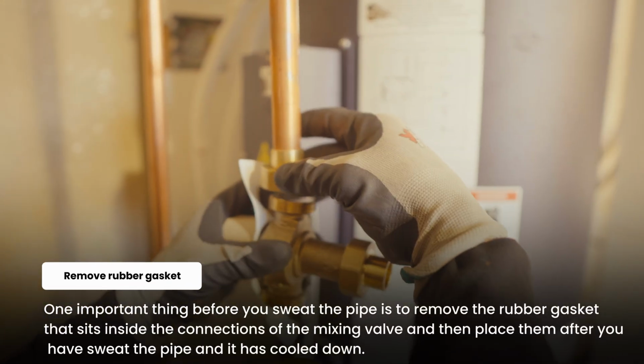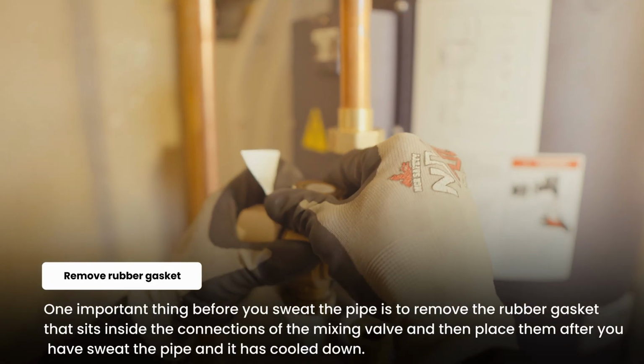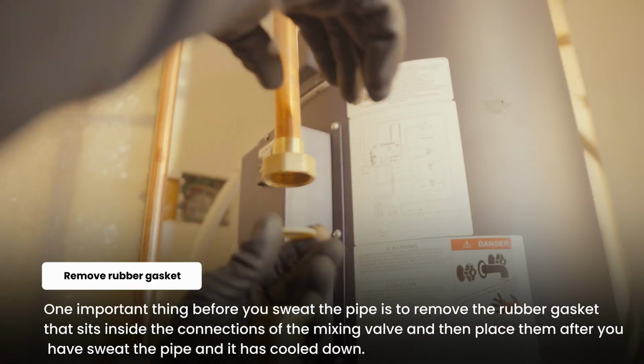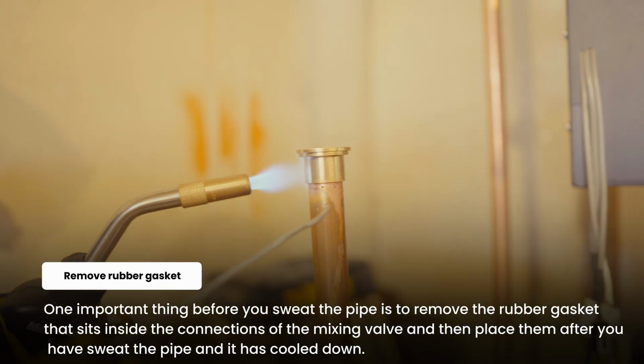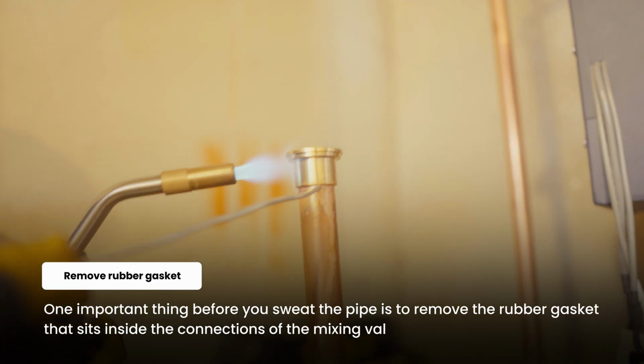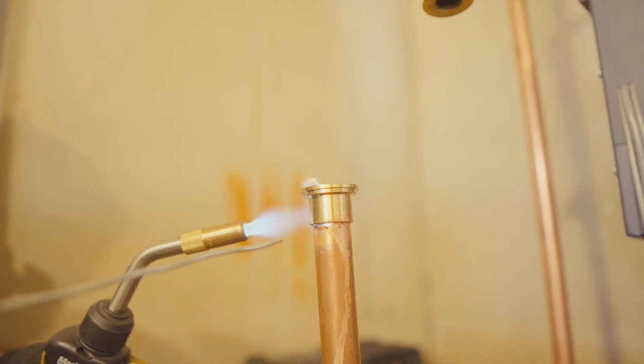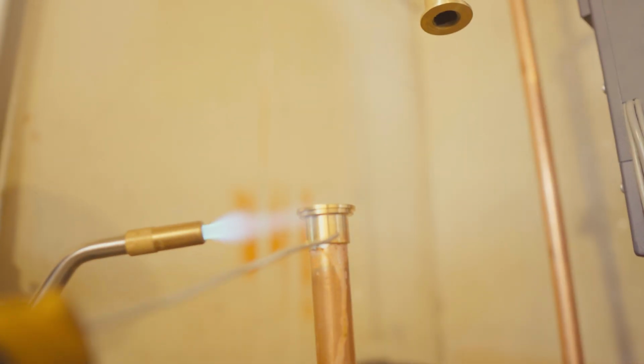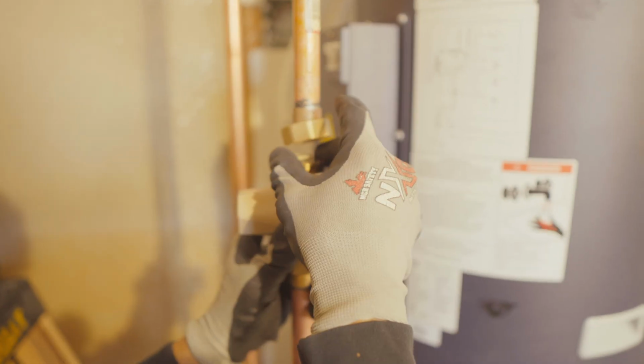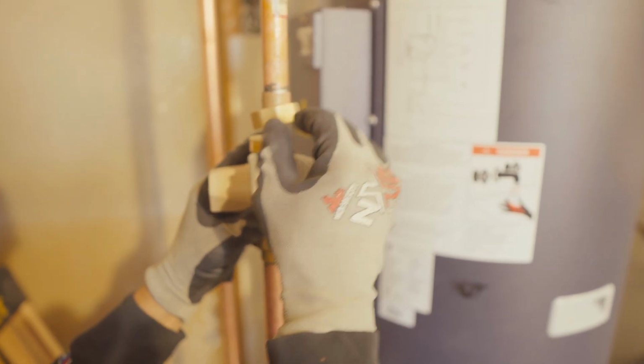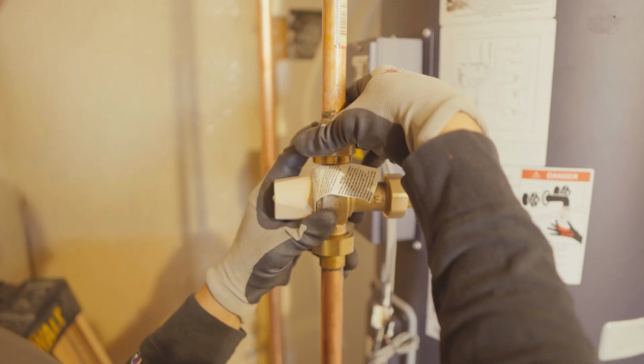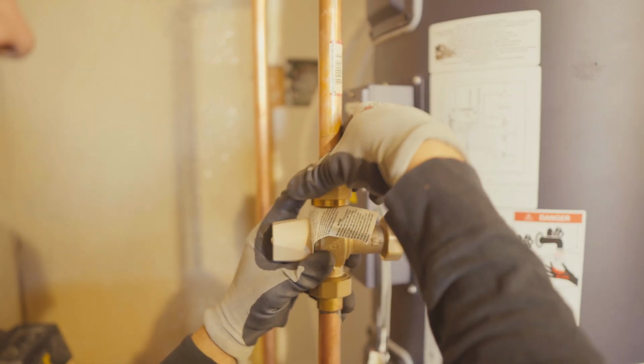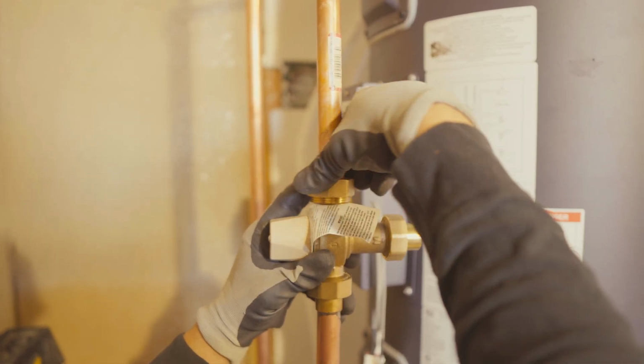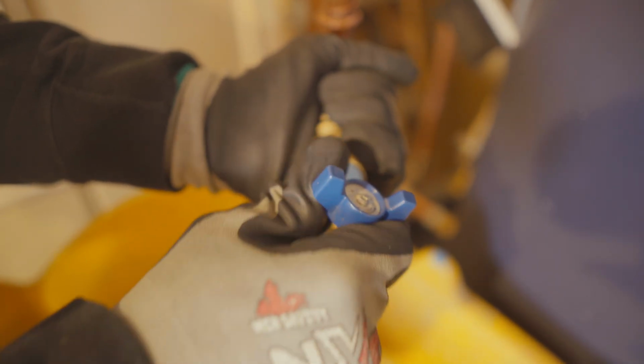One important thing before you sweat the pipe is to remove the rubber gaskets that sit inside the connections of the mixing valve. Without removing them, you risk damaging the gaskets with the heat from a torch. Place them back in after you have sweat the pipe and it has cooled down. The mixed water outlet from the valve can then be routed to the home's hot water distribution system.